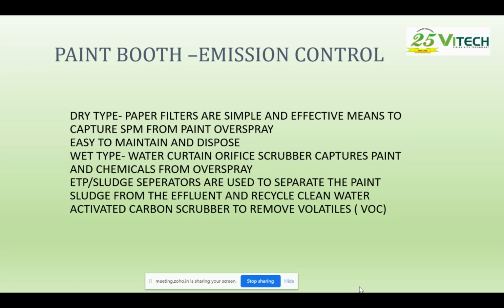In a wet booth, the paint forms a sludge in the tank, and if this sludge keeps accumulating, the water has to be removed and the sludge separated. Today we have equipment called sludge separators, which can work automatically or periodically. The contaminated water from the paint booth is pumped through a separator where, by centrifugal force, the sludge is separated, and the clean water can be recycled into the paint booth, so there is no discharge of water from the paint booth.